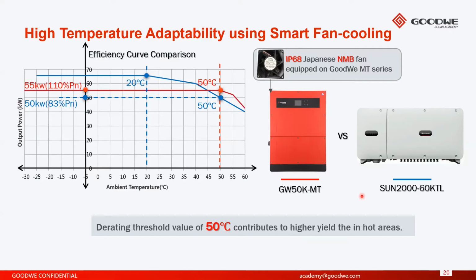So as you can see on the left hand side here, our inverter, the red line, is the GoodWe inverter, and as you can see, it starts derating from 50 degrees, whereas an inverter with passive cooling starts to derate much earlier. So we did internal in-house testing, and a number of other manufacturers actually start to derate from 20 degrees.